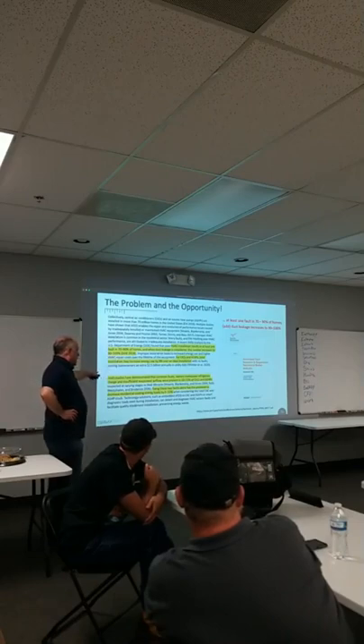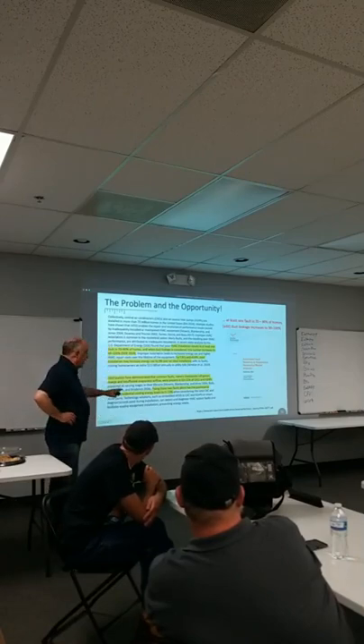This one was done by Pacific Northwest National Laboratories, and it said HVAC installations have a fault in 70 to 90% of homes. So 7 to 9 out of 10 homes have a fault. And when you consider duct leakage, it goes to 90 to 100%. This is a DOE study in 2018. For air conditioning and heat pumps, energy use is increased by 9% over ideal installation. And it really came down to inadequate refrigerant charge and insufficient evaporator airflow in 50 to 72% of systems. So in the residential segment, 50 to 72% of them don't have correct charge and airflow, right? Fixing those two faults alone is a 5 to 10% decrease in residential cooling loads.